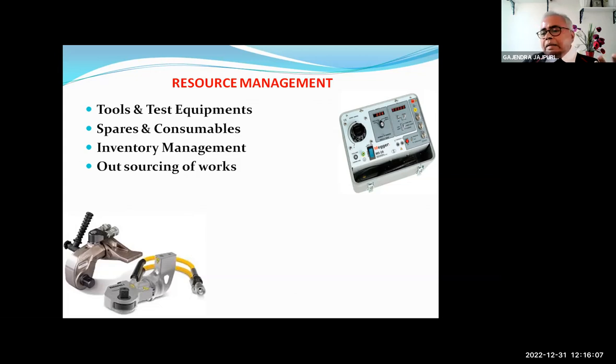Another thing is that degraded, damaged, or out-of-calibration tools and test equipment need to be disposed of on a regular basis as per the organization guideline. If it is outsourced, you will not allow use of out-of-calibration instruments - that is another benefit, as they will be able to produce documents showing it is a duly calibrated test equipment.